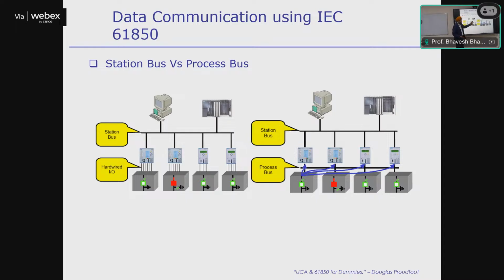Most substations now have IEDs hardwired from the breakers or from the CTs and PTs. At the station bus, we have IEC 61850, but this is where we want to go also—the process bus also should be IEC 61850 compliant, and it should be networked. Then you can share all this information from anywhere with everything.